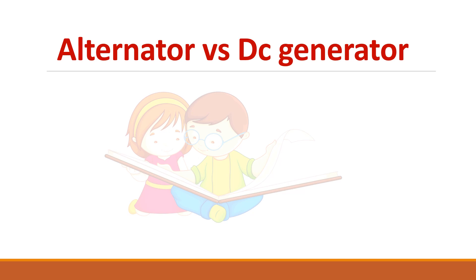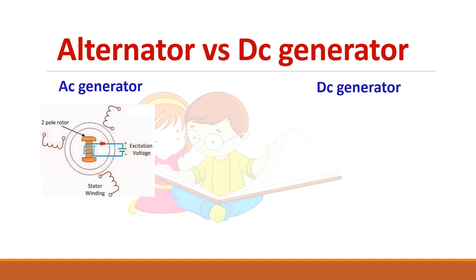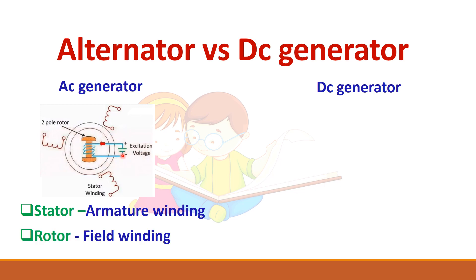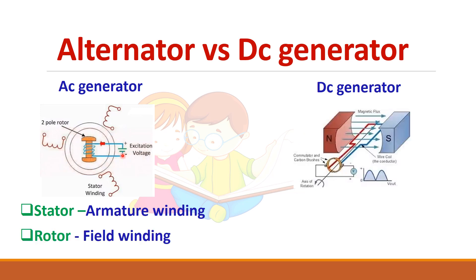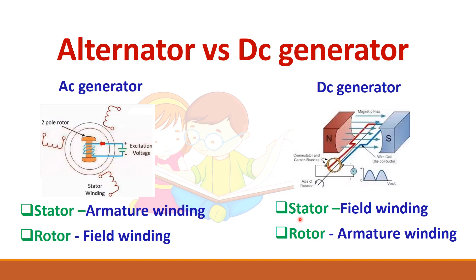Now we will see the difference between an alternator (AC generator) and a DC generator. In an AC generator, there are three-phase windings on its stator and a field winding on its rotor. In a DC generator it is just the opposite — in the stator we have the field winding, so the field poles are stationary, and the armature winding rotates in the magnetic field. So in a DC generator, the stator has the field winding and the rotor has the armature winding.